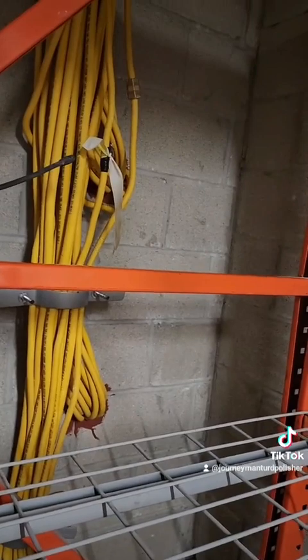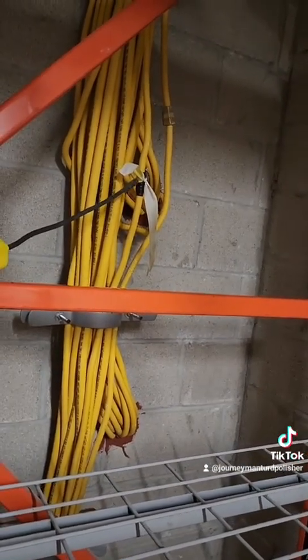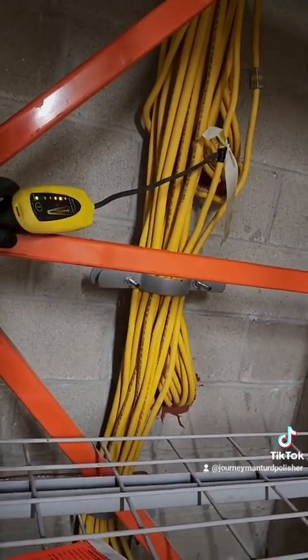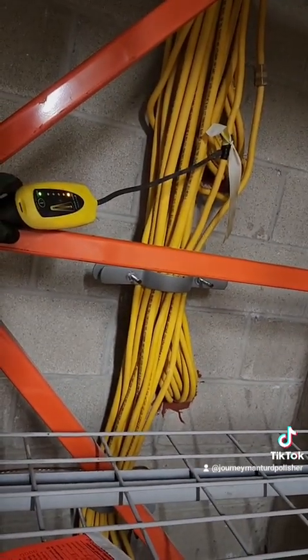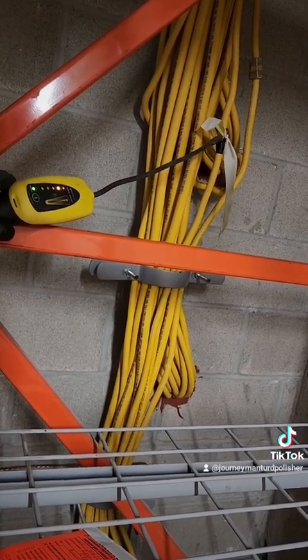I've never been a big fan of the whole high sensitivity, low sensitivity setting. I would much rather see something in a numbered format. That's why I'm a fan of the Tech refrigerant leak detector. See, now we finally pick something up, but only on the highest sensitivity level, which a lot of guys, from my experience, don't even use.